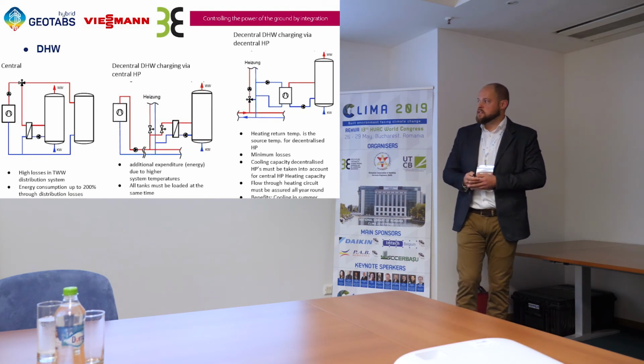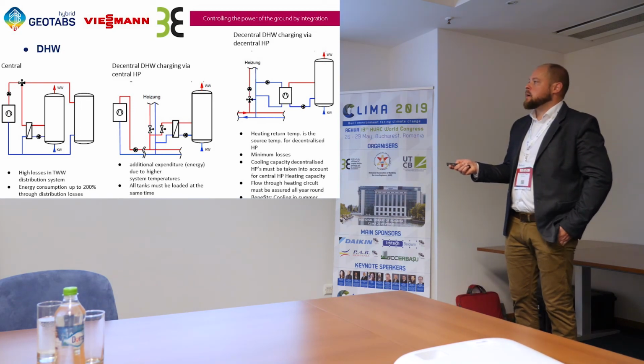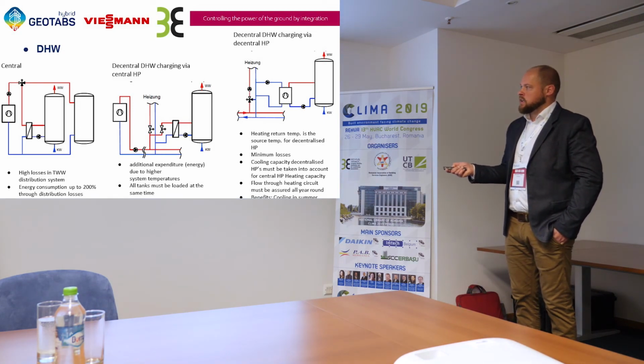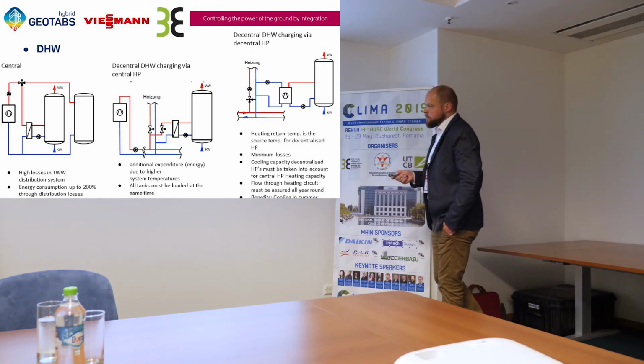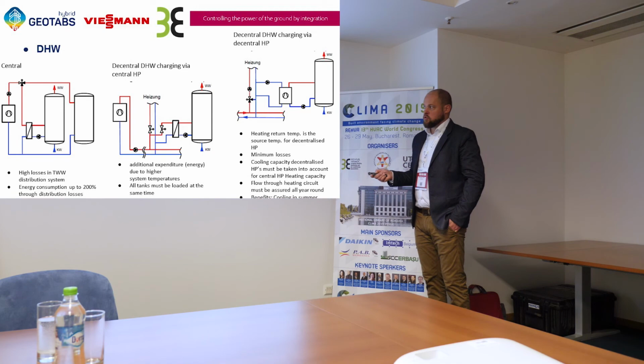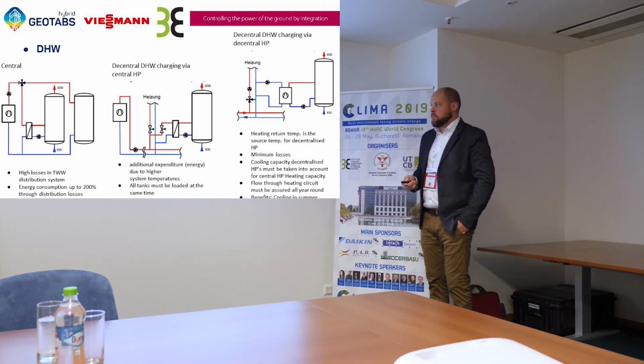There are many different systems that can be used. So here you see the heat pump with a normal buffer tank for the heating, and then we have a plate heat exchanger to load domestic hot water inside the buffer tank. You can control this pump by control of speed, for example, so you have a higher charging temperature, or we can use a mixing valve to regulate the charging temperature in this example. This is an off position, so it means that we make heat for the building, or we are charging the domestic hot water tanks.